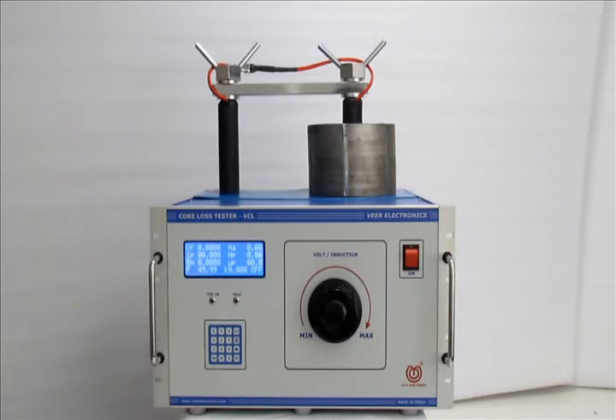For that purpose, it is very important to test core losses of stacked core using this tester to determine whether a core is damaged or not, or any kind of mixed material is used inside of core or not.